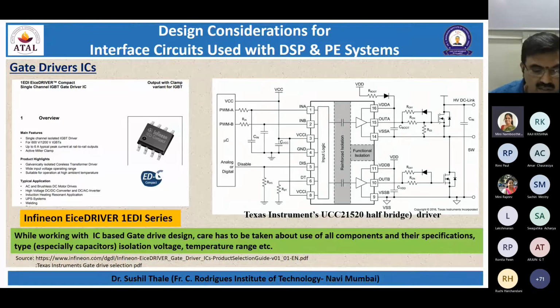In traction applications, my ambient temperature requirement comes to 60 degrees as the minimum requirement. If I use a commercial product design, I may work with 40 degrees Celsius as my ambient temperature. In certain specific designs, I may go up to 45 or 50 degrees Celsius. In some cases it can be force cooled, water cooled, or naturally cooled. While working with traction systems, we work with 60 degrees Celsius as ambient with a naturally cooled system.